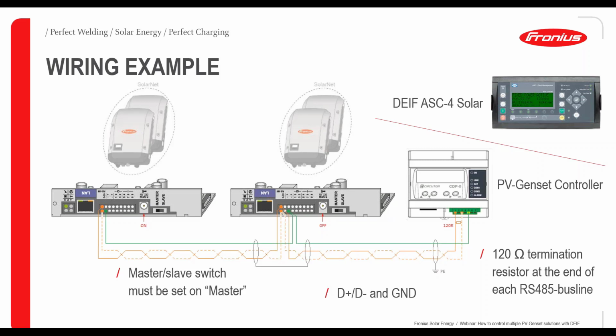And last but not least, we don't forget the termination at the end of our Modbus bus line. So we have a 120 ohm termination resistor, which we need to set. So looking at this Modbus line, we have on the left-hand side on the data manager an end point of our Modbus. So here we need to set the termination to on.